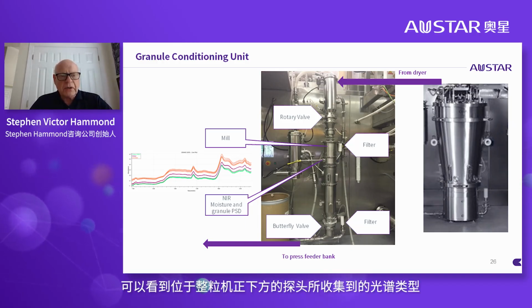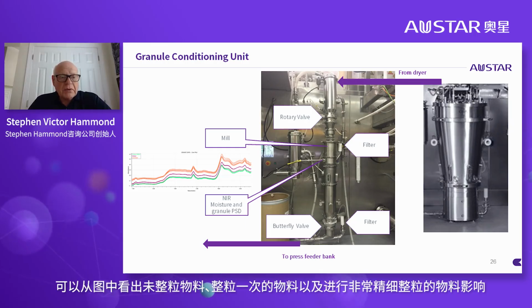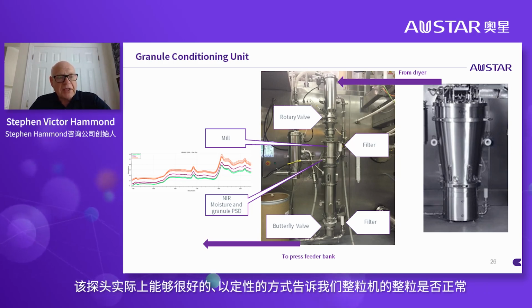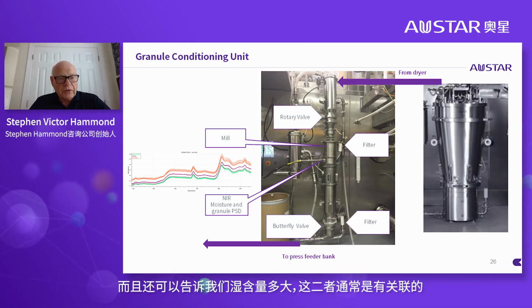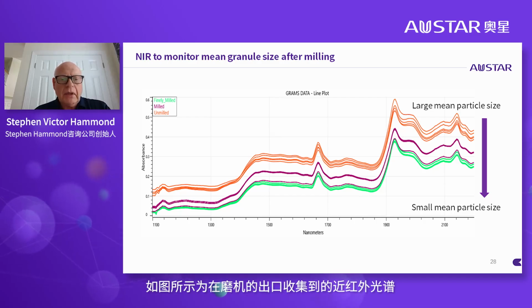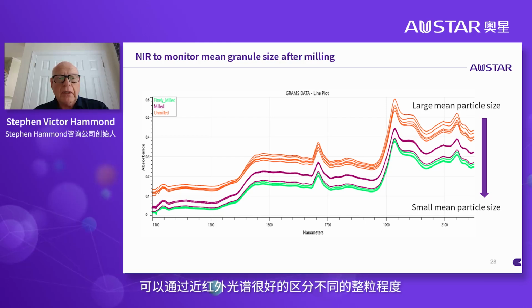And you can see the type of spectra that can be collected from that probe inserted just below the mill. And the diagram you can see shows the effect of unmilled material, milled once material, and then very finely milled material. The probe is actually able to quite well, qualitatively at least, tell us whether the mill is milling these granules as they normally would do, and also to tell us what the moisture content is, which is often the two are related. Here I'm just showing the near-infrared spectra collected on the output of the mill, just so you can see how well the different levels of milling are separated in the near-infrared spectra.